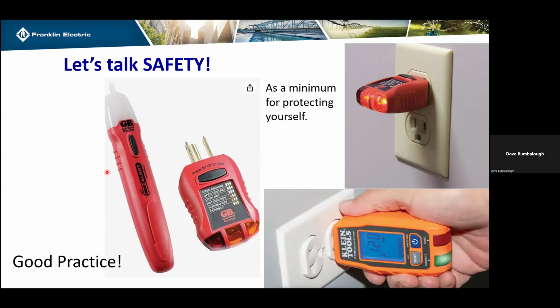There are some kits that you can buy. Honestly, all three of these I have in my toolbox. Before I turn a disconnect off, or open up a metal cabinet, or touch a device, or even the plumbing, especially if it's metal plumbing, I'm going to take my pen and test to see if there's some kind of leakage going on there. I'd much rather have the pen beep at me or flash at me than touch it and get a tingle. In some cases, that tingle could translate into something more severe. So you want to be very careful there.